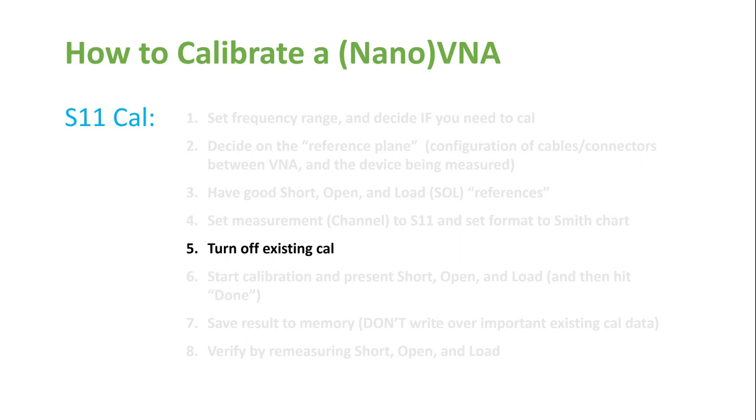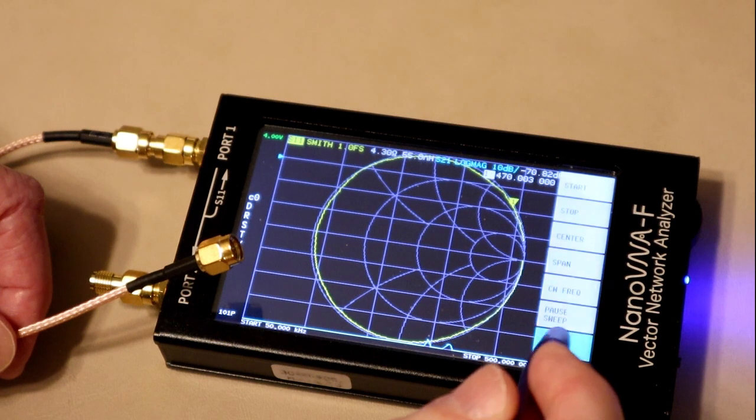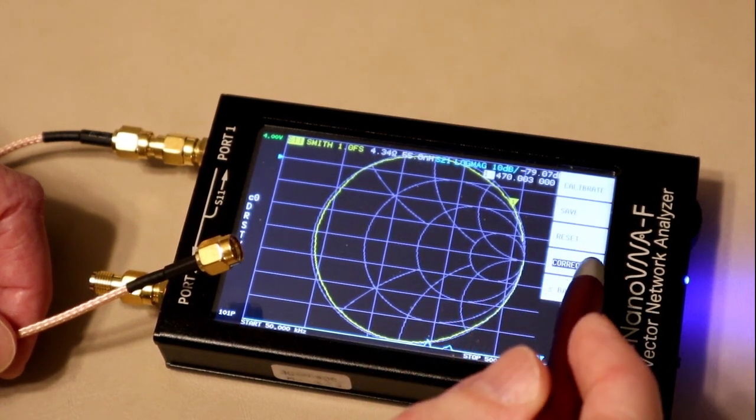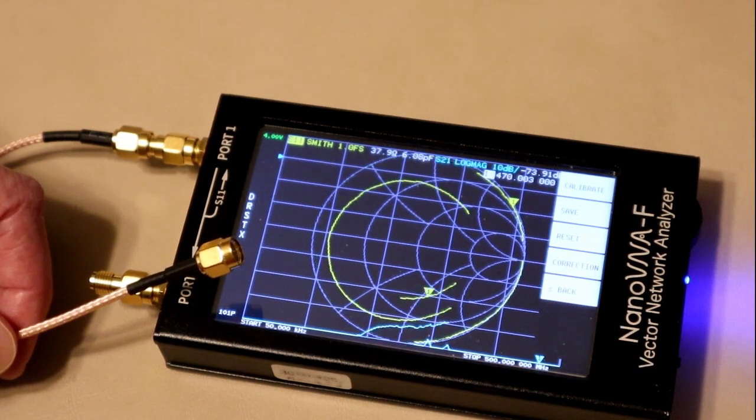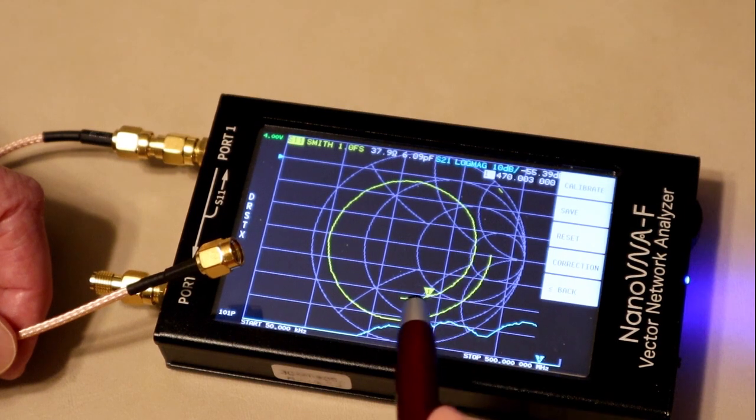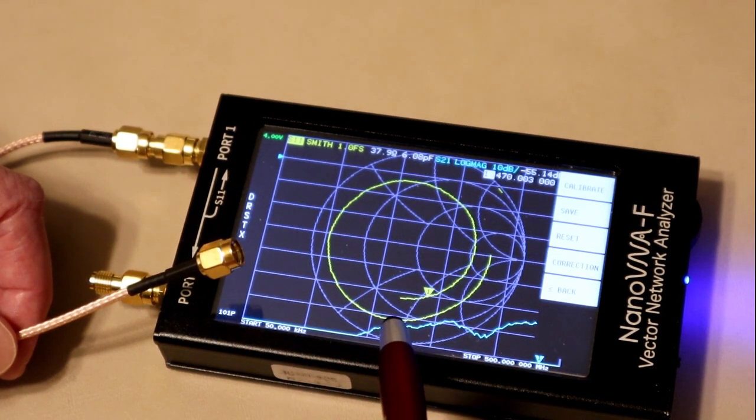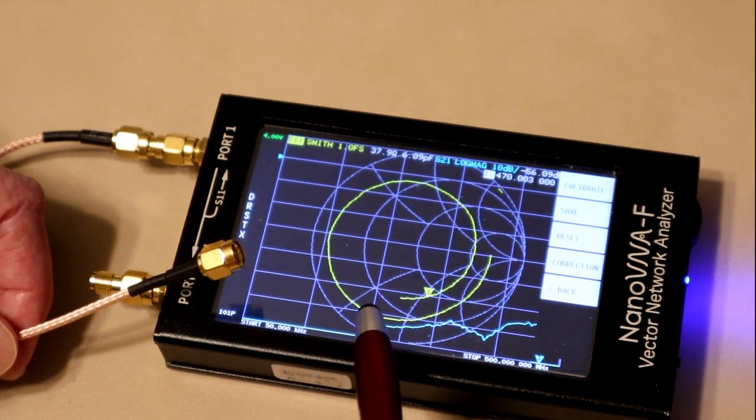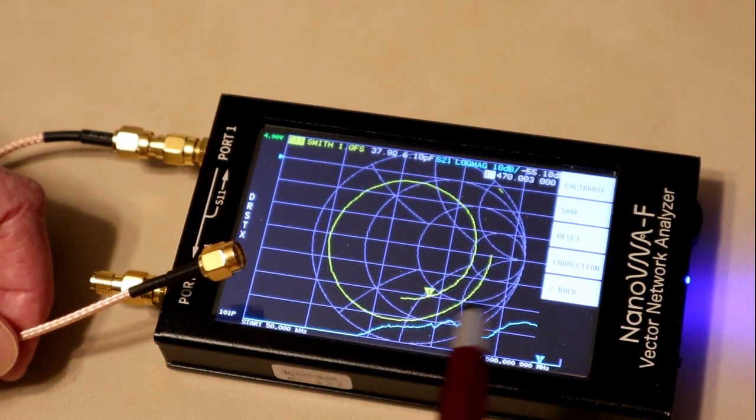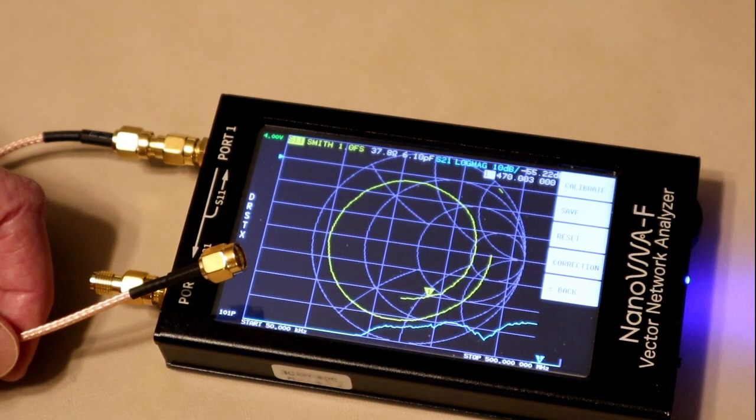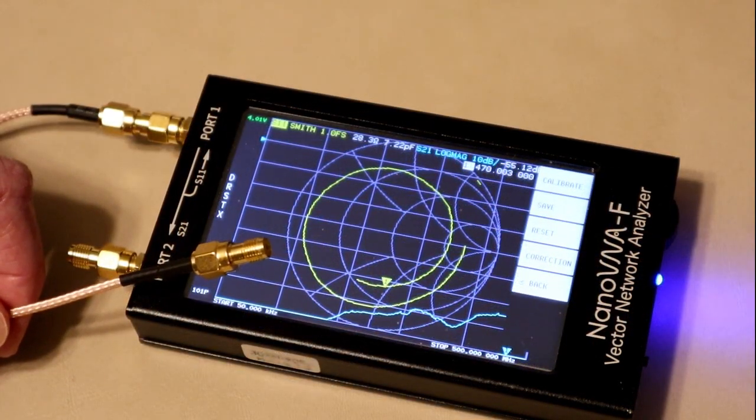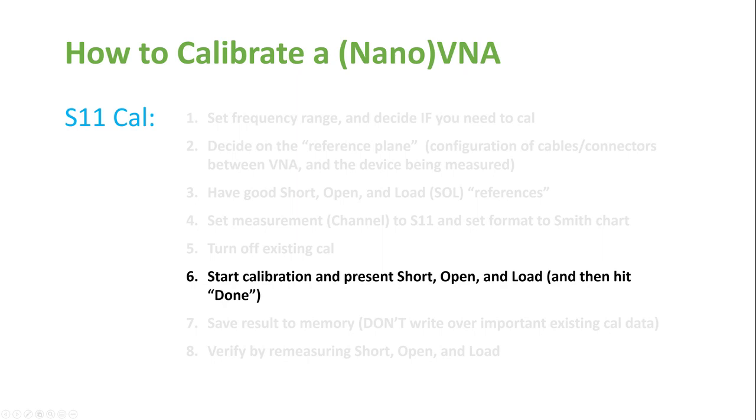I'm currently in log magnitude display, so again, I'm going to go to the menu, and I will select Format and Smith Chart. The next step is to turn off the existing calibration. So I will hit Back from the menu I was in, hit Cal, and I hit Correction to unhighlight it. Notice when I did that, that the S11 plot is now vastly different. This is due to the inaccuracies in the circuitry of the device itself. Remember when we talked about why you want to calibrate? One of the main things was the calibration fixes inaccuracies in the instrument itself. When I turn off the correction, those become blatantly obvious.